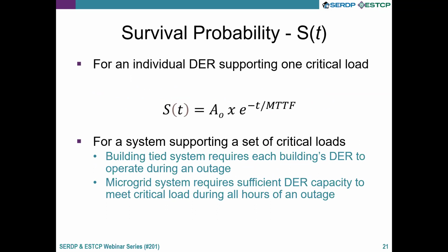How do those parameters relate back to resilience, which we quantify by survival probability? It's quite simple for an individual generator tied to a single building. The survival probability equals the availability probability, usually in the high 90s percentage, and then it decays exponentially with time, with a time constant equal to the mean time to failure. So if we don't have high availability, because the system is often down for maintenance or repairs, the survival probability is inherently low. If we have a very long mean time to failure, that won't decrease much over time, but a short mean time to failure will decay with exponential probability quite quickly.